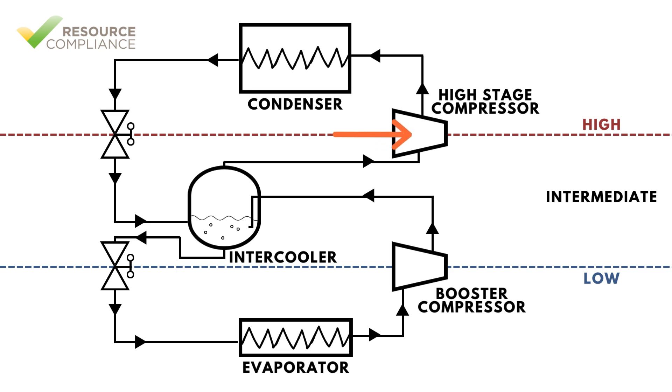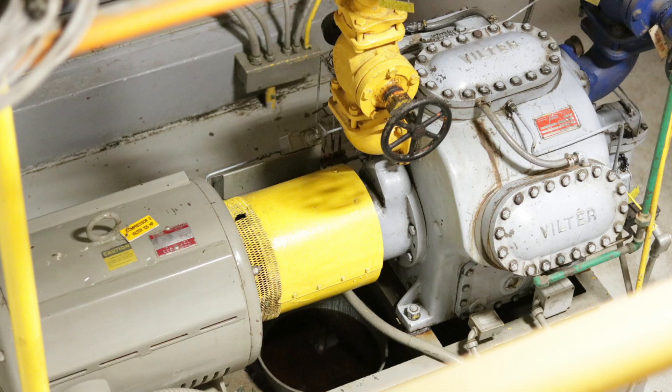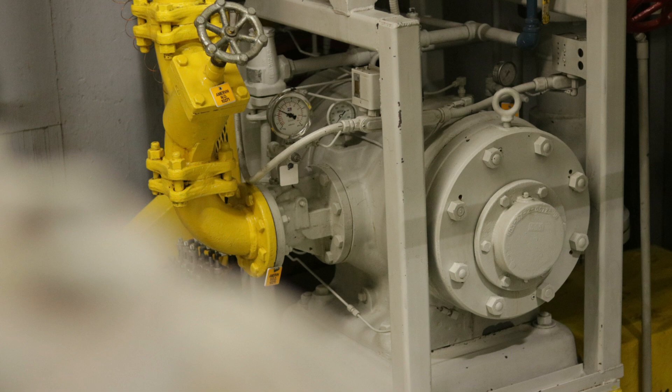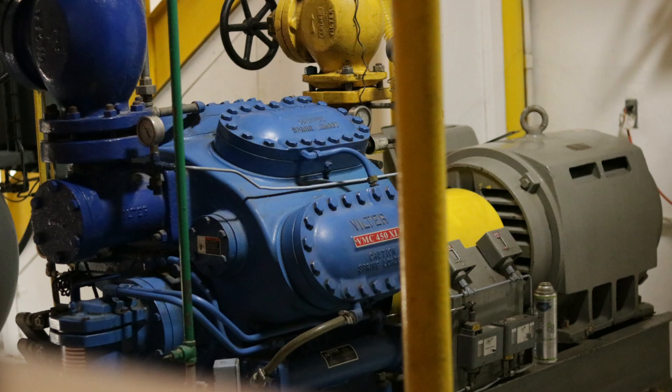That vapor is supplied to the inlet of the second stage compressor, which is typically called the high-stage compressor. Removing the superheat from the vapor supplied to the high-stage compressor results in a discharge temperature at the high-stage compressor that will not break down lubricating oil or damage the compressor.